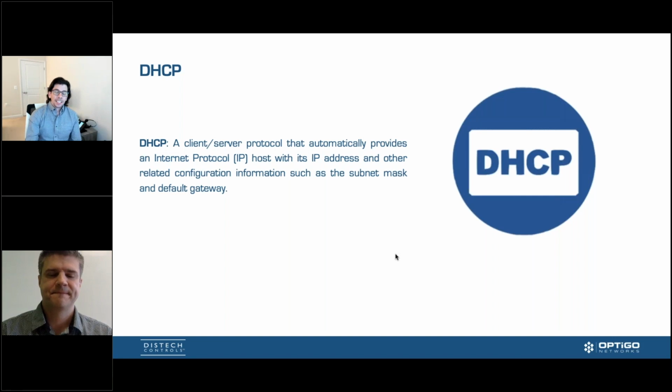So perfect. This is what we hope most of you are using if you're doing a controls network. I know typically in the past, everybody's used static IPs because they're easy. You pick an IP address, you assign it, you know where it is, so there's no guesswork, and then off you go. And that worked very well when we had systems with very few hosts, very few controllers or devices that had IP addresses. Now we're getting into systems where we have IP addresses at a light bulb, at a light switch. We have IP addresses everywhere now. So we're now getting systems where there's thousands of IPs, and doing static assignment isn't going to work. It'd be very difficult to maintain that.